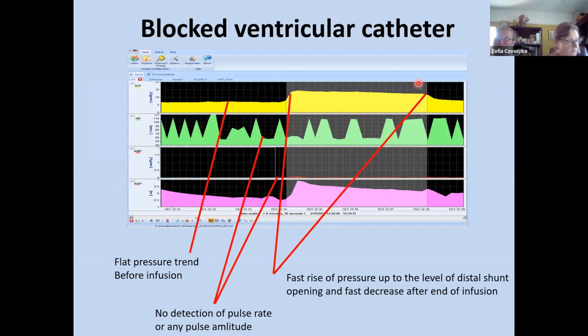And here we've got a typical result of an infusion study for a system with proximal blockage. We've got flat pressure. You remember, these are recordings from the shunt chamber. So on the baseline we've got flat recordings without any pulsation, no detection of the pulse amplitude, and consequently no detection of heart rate. The system is still draining distally. The pressure is nicely stabilized.